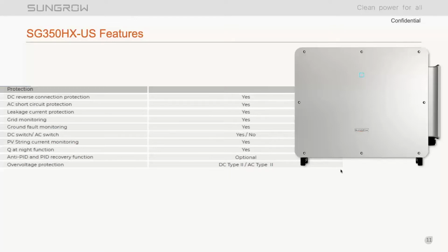Q at night function is still integrated, and that's becoming a more and more popular request from projects because the reactive power at night in areas where the grid is weak again is something that utilities are starting to ask for a little bit more. And there's also a slight influx that we've seen in the trends across projects in the CNI space, definitely in the utility space. But there's an influx of monetizing that reactive power at night. So there are some incentives for developers and operators to provide reactive power at night, and the 350 has that capability.